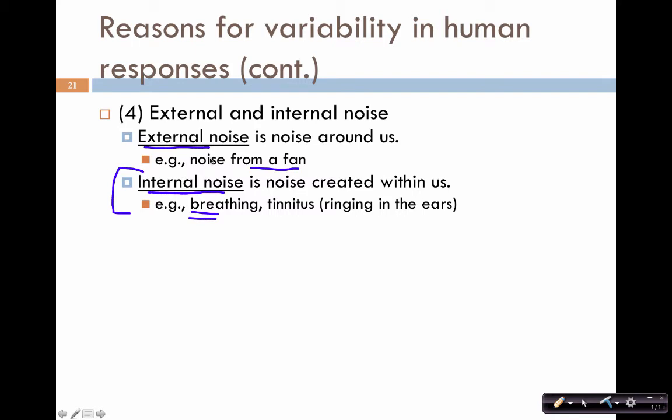And if you didn't know that, you might come to the conclusion that the person has a hearing loss when in fact it was a noisy background. On most clinical tests of audiometry done by audiologists, they're done in rooms that are sound treated, so there's an absence of external noise, or at least a minimization of external noise. And that would be specified on the test form.